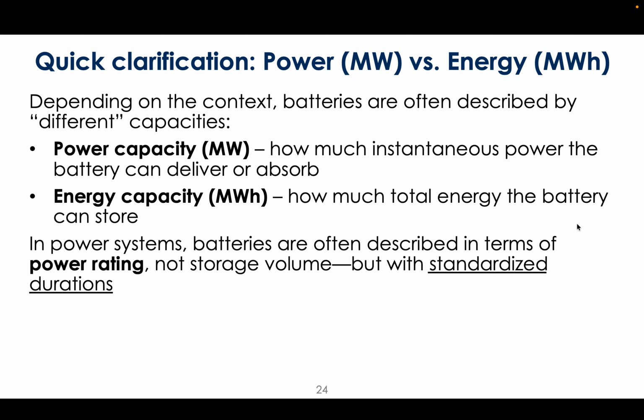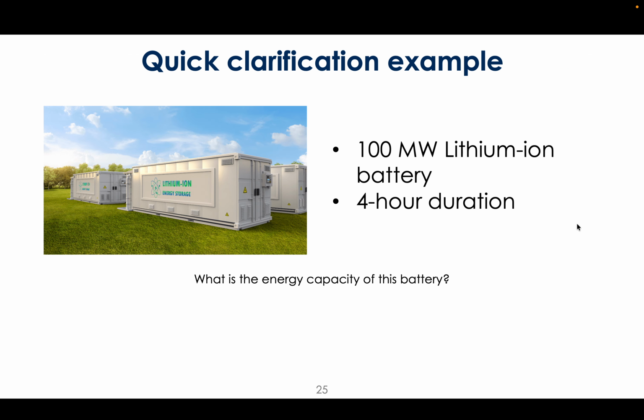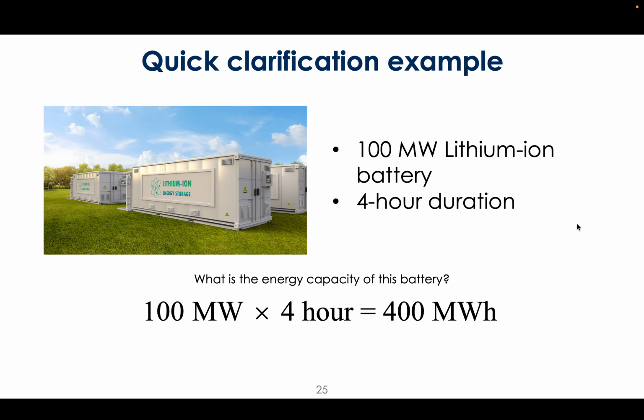That's how we think about capacities for grid based storage—we're in the power capacity world. So a 100 megawatt lithium ion battery with a 4 hour duration is 100 megawatts times 4 hours, or 400 megawatt hours. Pretty straightforward.